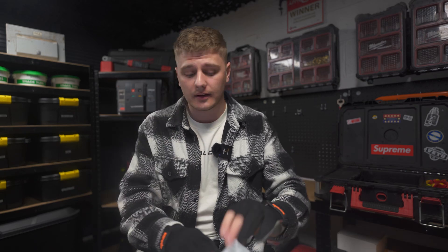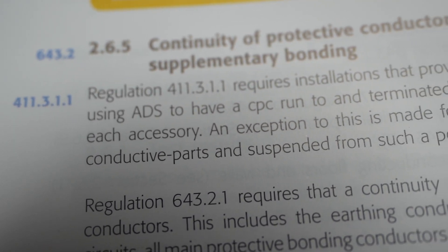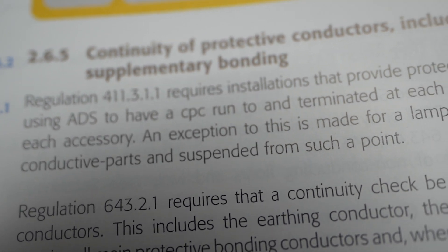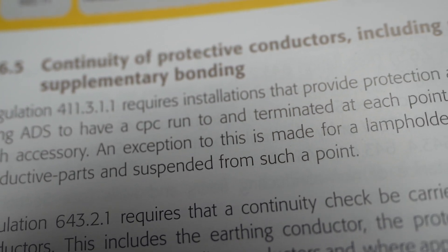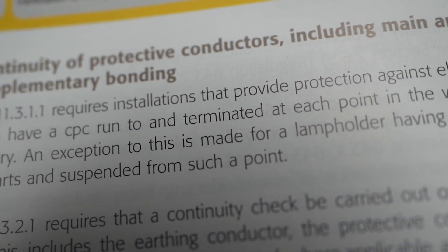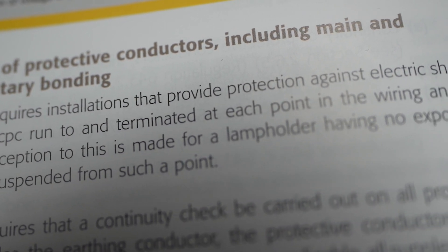As electricians, the regulations require us to do two things. The first thing is regulation 411.3.1.1, which requires that installations provide protection against electric shock using ADS, and that you have a CPC run to and terminated at each point in the wiring and at each accessory. An exception is made for a lamp holder having no exposed conductive parts. So basically, you need to take an earth to every junction, every point, every accessory of a circuit.